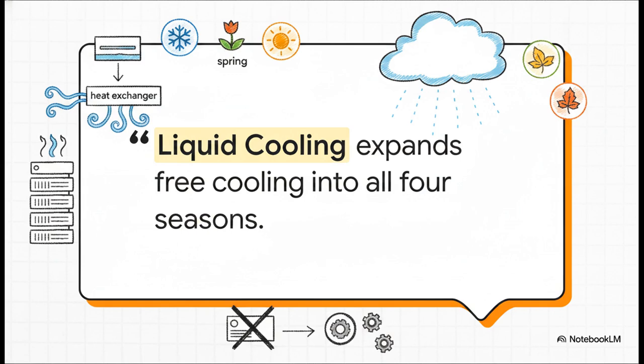Because of their immense heat output, AI servers are ironically allowing data centers to do what used to be impossible: achieving year-round free cooling. Facilities can use the outside air not just in the dead of winter, but right through spring, autumn, and even on warm summer days, keeping those heavy compressors permanently offline.